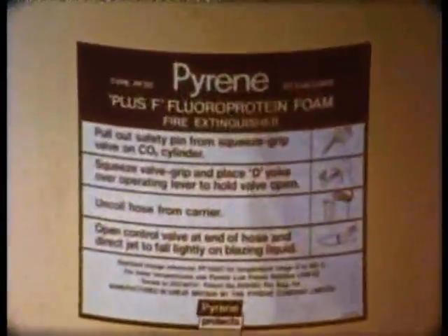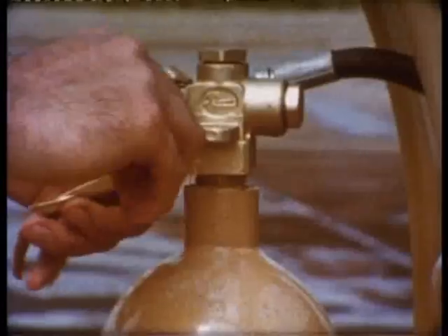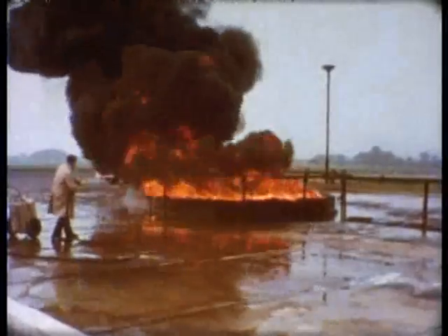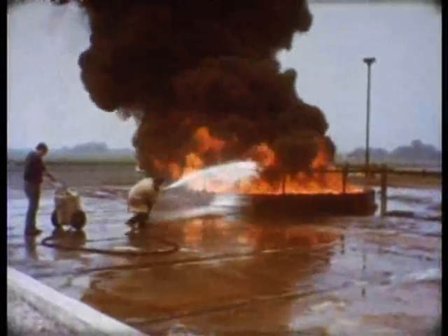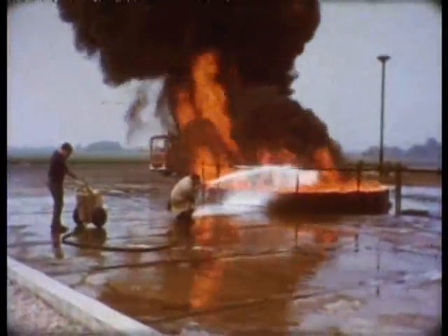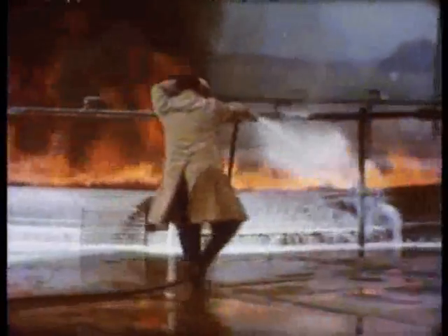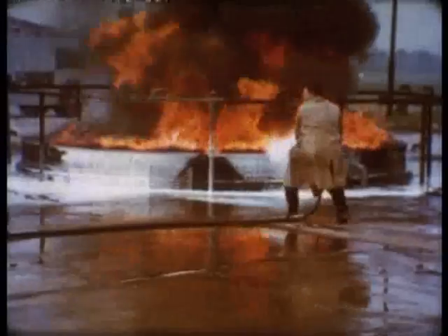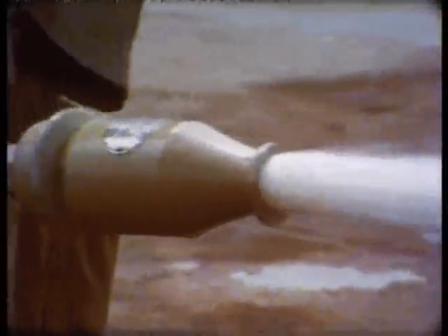When fighting larger Class B fires, a two-man operation of the foam trolley unit affords greater maneuverability, and by aiming the foam beyond the eye of the fire, it allows it to build up and float back over the surface of the blazing liquid, sealing it off. Do not direct it into the liquid, since the discharge will merely drive the foam below the surface, thus rendering its purpose ineffective. As is well illustrated, when correctly applied, foam will progressively smother quite large areas of flame.